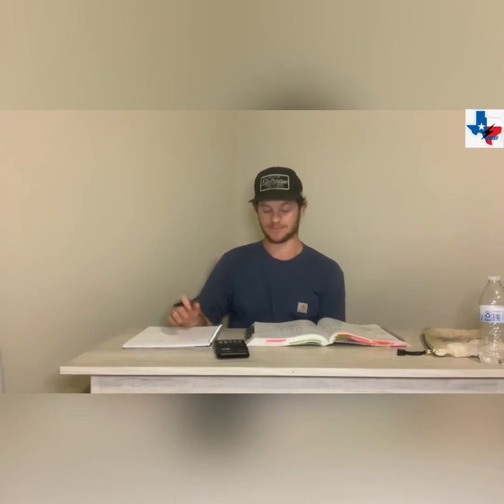All right, and the next thing we're going to size is our OCPD. Like I said, you got that 65 number up there, keep that 65 number. So, 65 amps, and I said we're using dual element time delay fuses. Like I said, flip right back into 430.52, and this is where you're going to find your percentage. So, dual element time delay fuses, 175% for both single phase and polyphase motors.